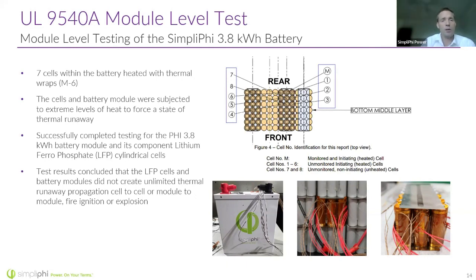Test results concluded that our LFP battery cells and modules did not create unlimited thermal runaway. So by getting multiple battery cells to off-gas, catch fire, and produce additional heat, we didn't end up with a chain reaction that made all the other battery cells around them do the same. This certification, this test procedure, is what allowed us to move forward in the testing process.